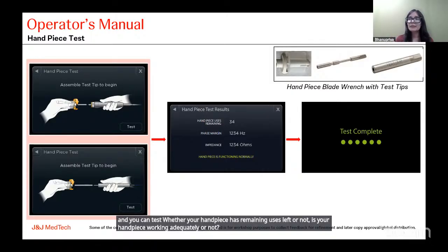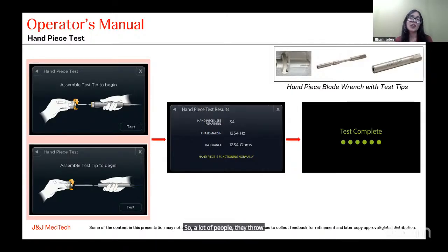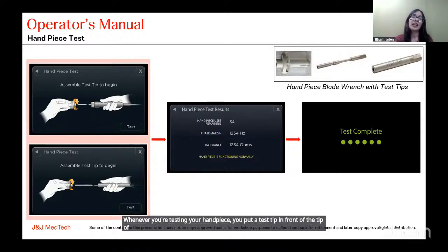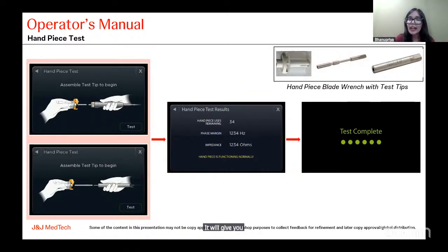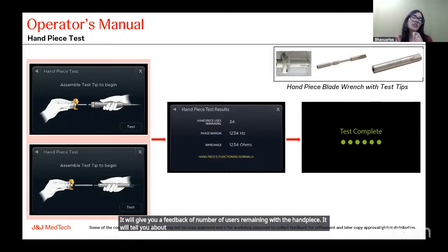So a lot of people throw away something called a test tip. Whenever you get a handpiece, it comes with test tips. Now, what is the benefit of a test tip? Whenever you're testing your handpiece, you put a test tip in front of the tip of the handpiece, you click on handpiece test, and the system will automatically test your handpiece. It will give you feedback on the number of uses remaining with the handpiece. It will tell you about phase margin and impedance.